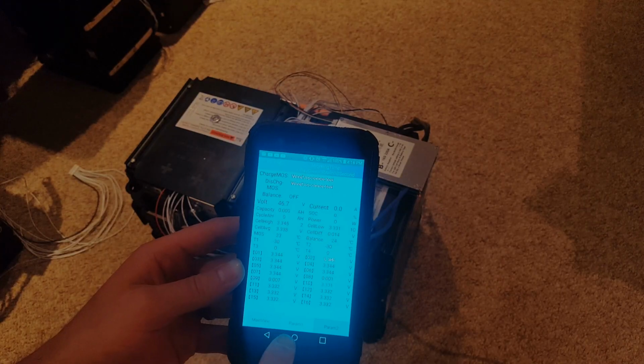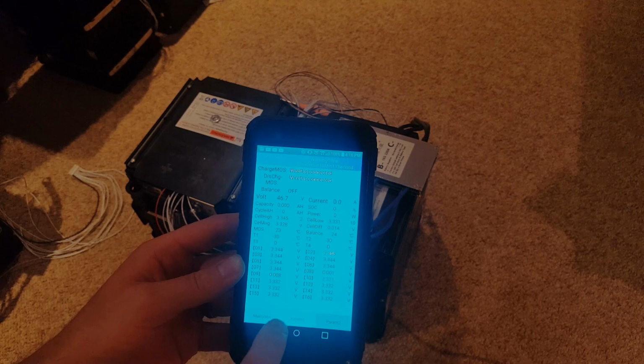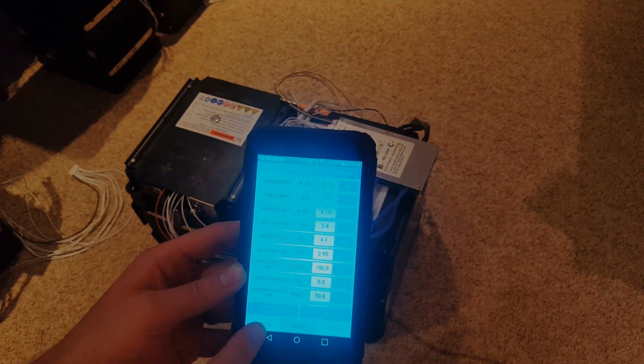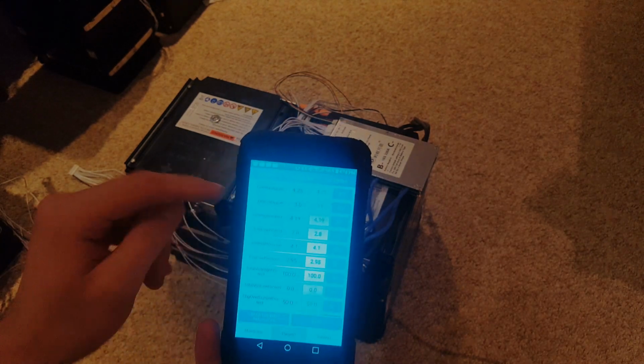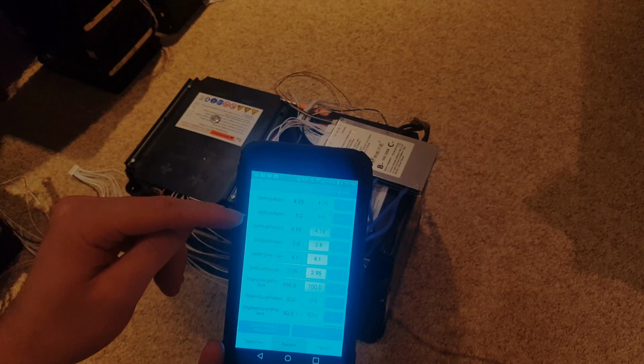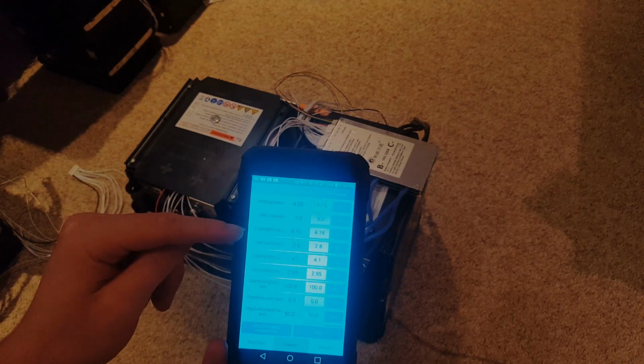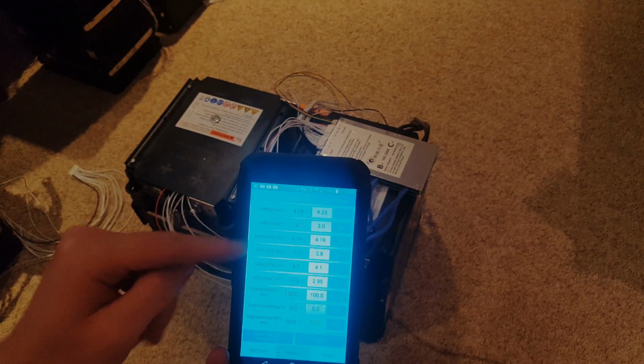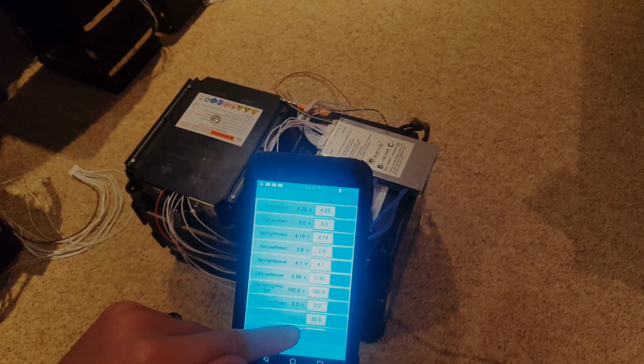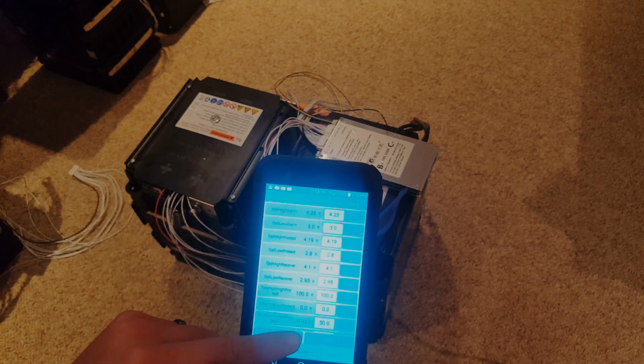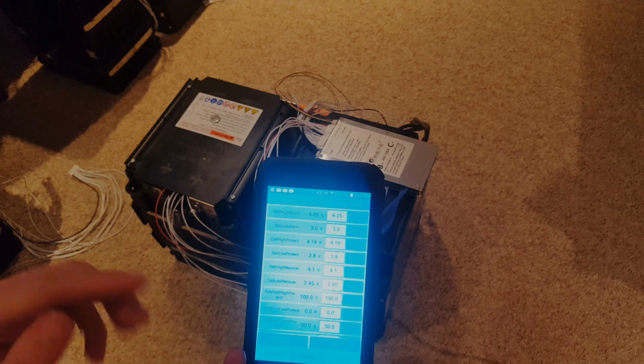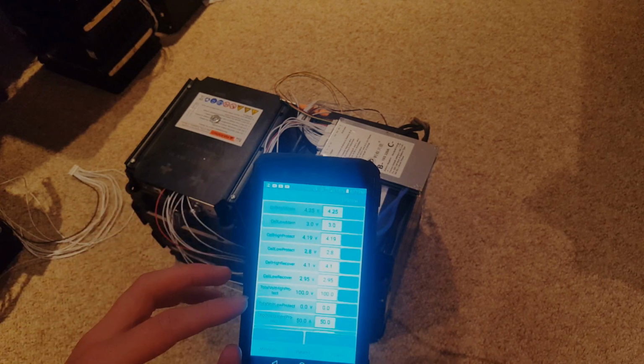To change all of this, you go to parameter 1 down here, and it brings up all of your parameters for the BMS, like the cell high voltage alarm, low voltage alarm, high voltage protection, low voltage protection. You can see right now that's all set up for 3.7 volt nominal lithium NMC, so we need to go through and set this all up for lithium iron phosphate.